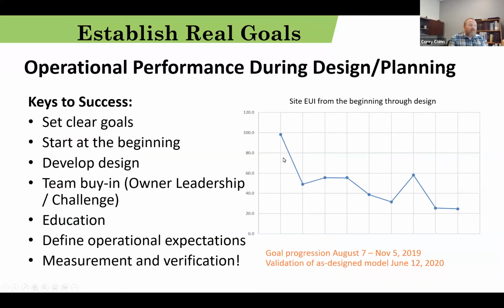So we took our goal from 50% savings, to get them down to 50 kBTU per square foot per year, to 30% savings over the Colorado Clinic, to get them into the upper 30s. And what you can see here is when we cast a vision early and we are all working towards it, we continuously improve the results. What you see here in this spike is the result of our goal setting and energy modeling through the whole project. This spike here is a recalibration of our baseline to make sure we weren't getting too out of whack before we did a final detailed analysis and wound up at a goal of 22 kBTU per square foot per year. So set clear goals, start at the beginning, develop the design properly, and you're gonna see this continuous decrease in your energy consumption and your costs.